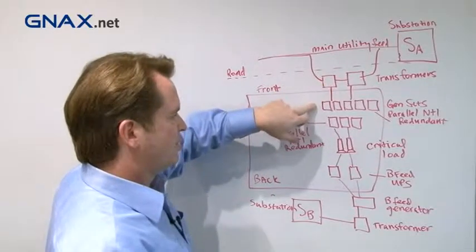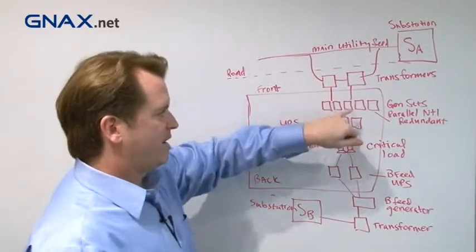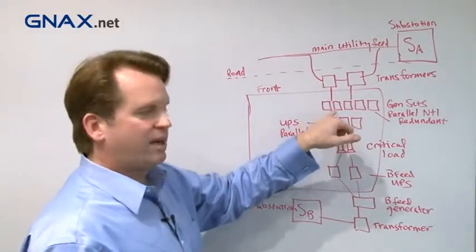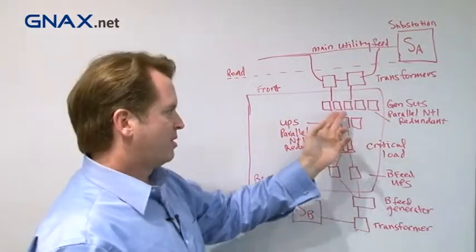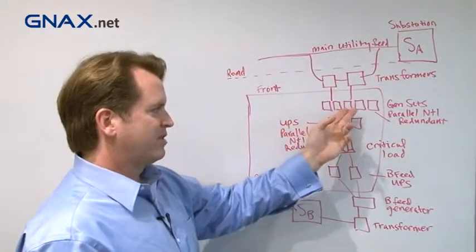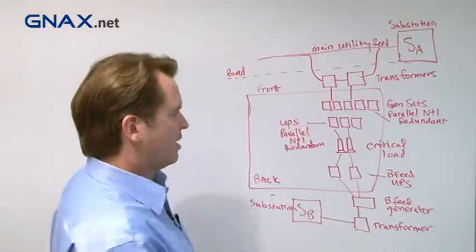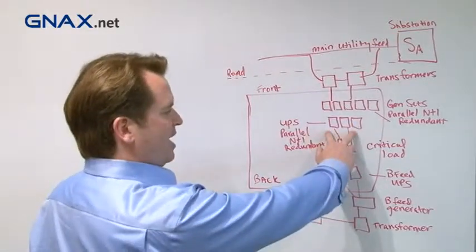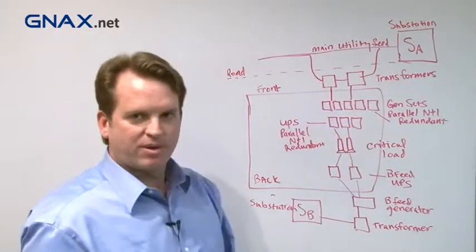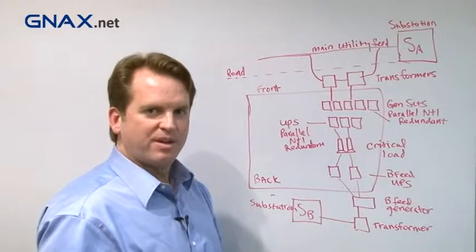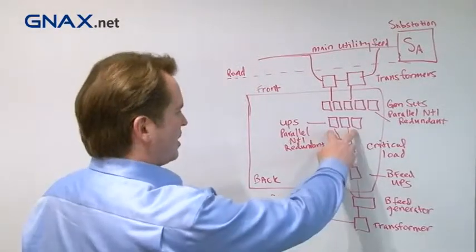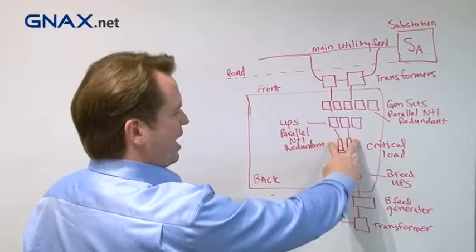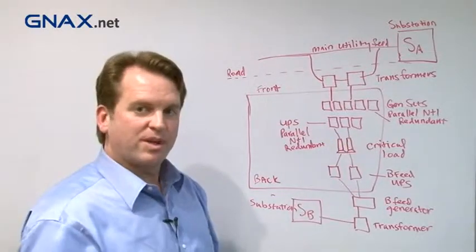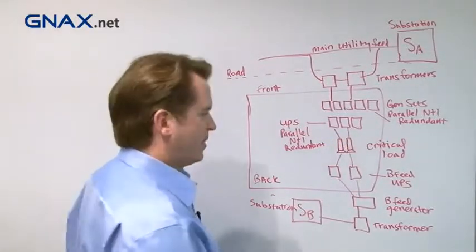These feed through gen sets. We've actually set up multiple parallel N+1 configurations for clients that only take a single feed, giving them a higher level of redundancy. These feed primary A feed UPSs, which are also parallel N+1 redundant for more redundancy. Those feed a primary A feed for your servers, otherwise known as critical load in the facility.